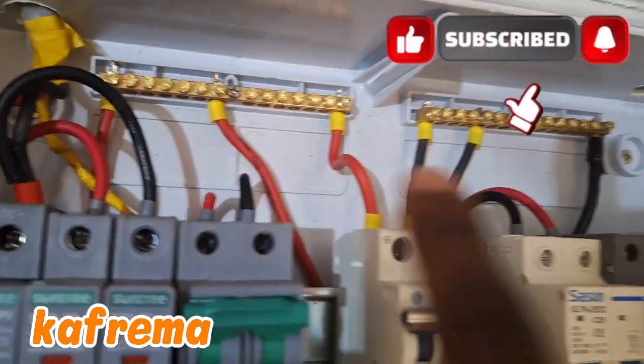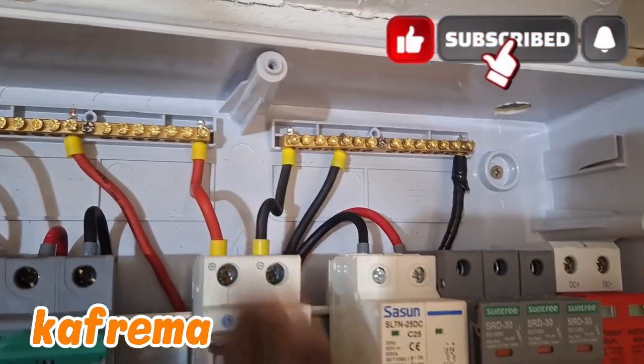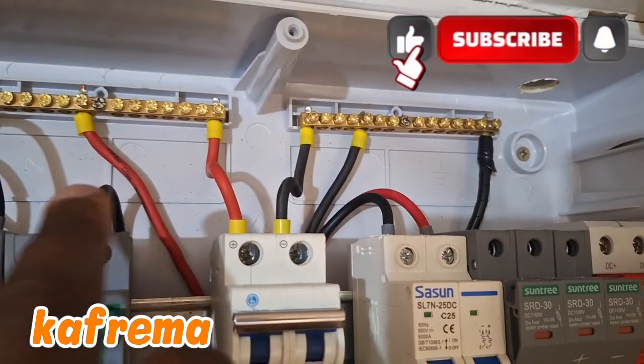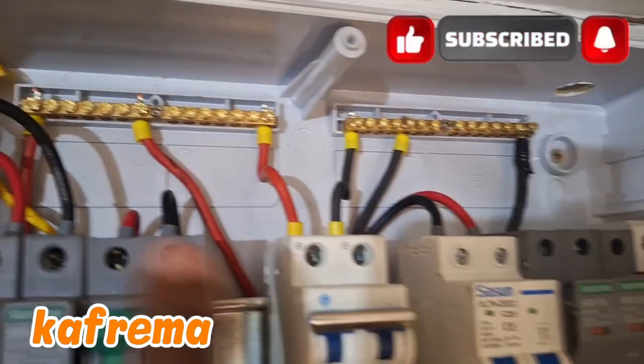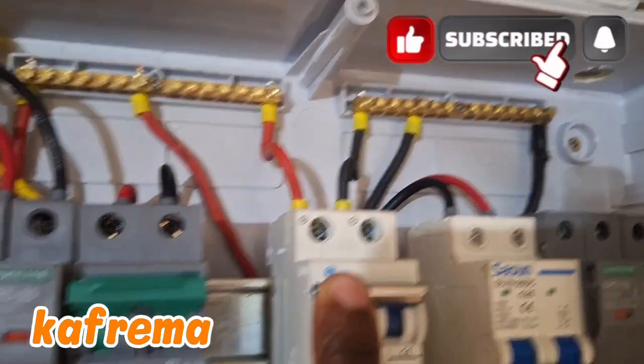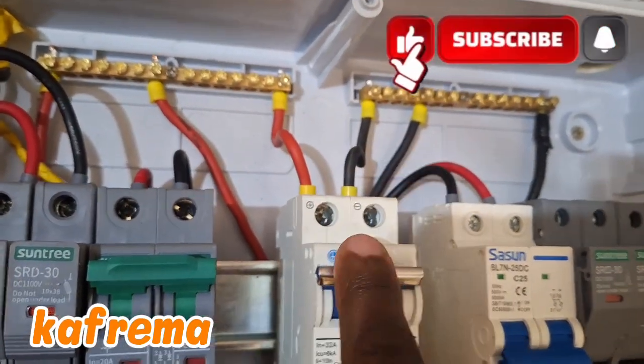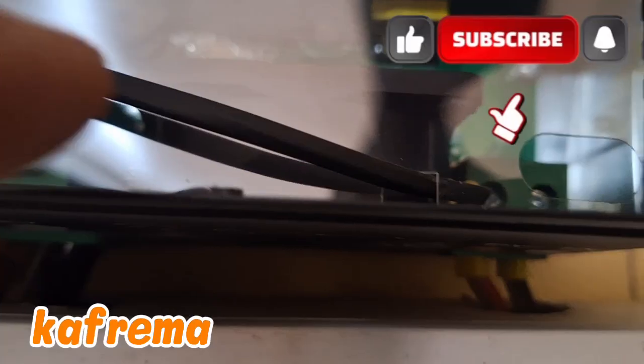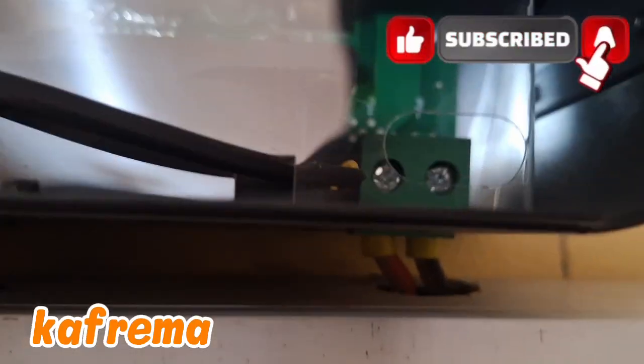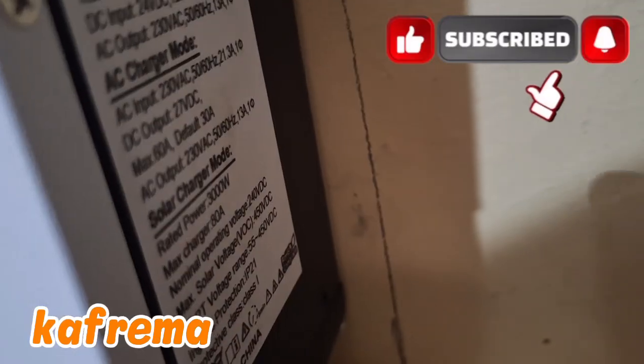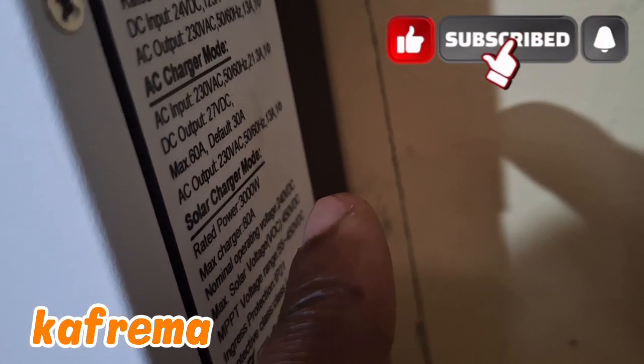Also, you have two bus bars, a positive bus bar and a negative bus bar. Both arrays can now be combined. You combine this array and this array, and you have one output to the inverter: one positive, one negative. This is the PV input. The PV voltage should be less than the VOC. Remember, here at the side, you are given the maximum VOC. Maximum solar voltage VOC is 450.